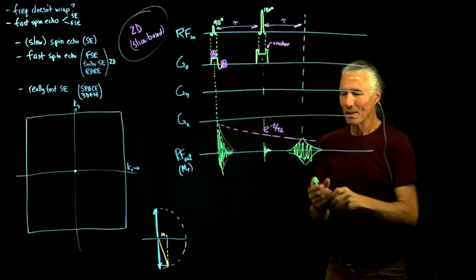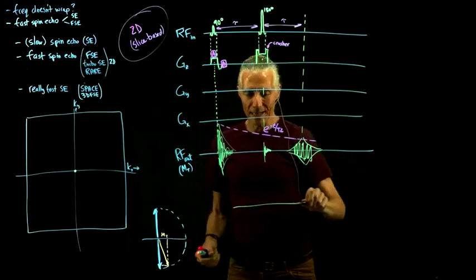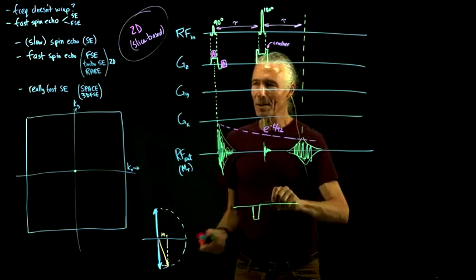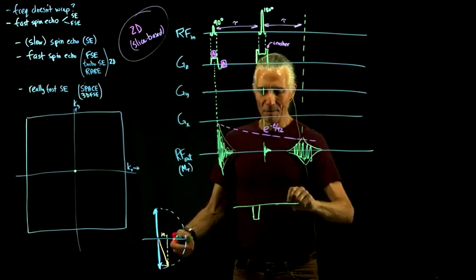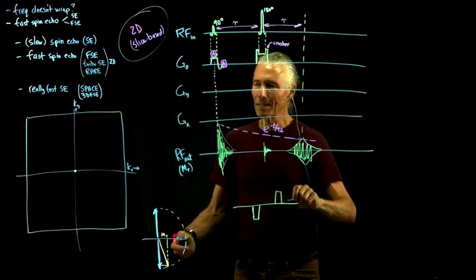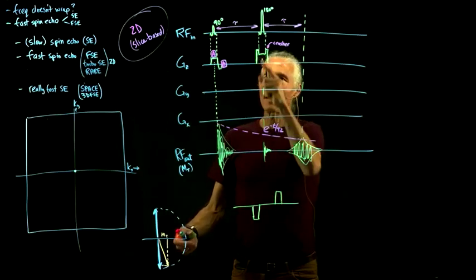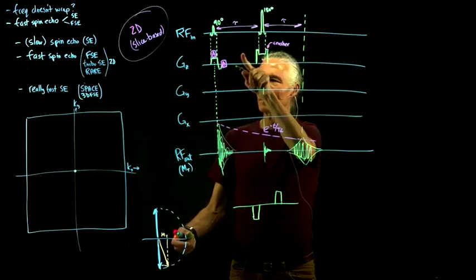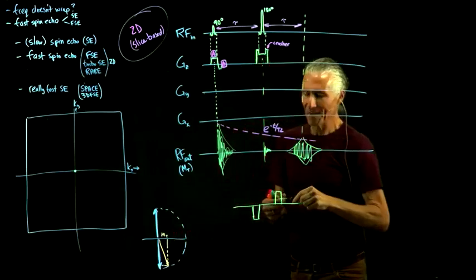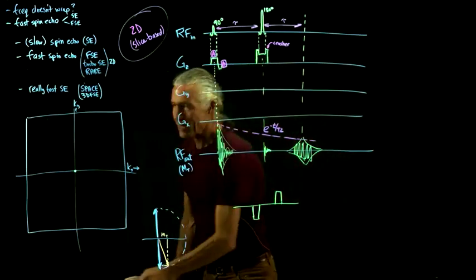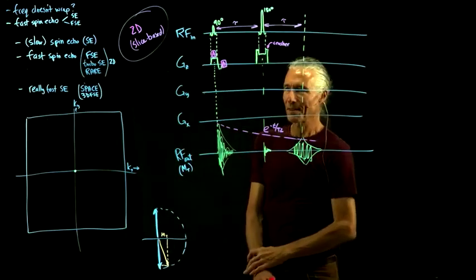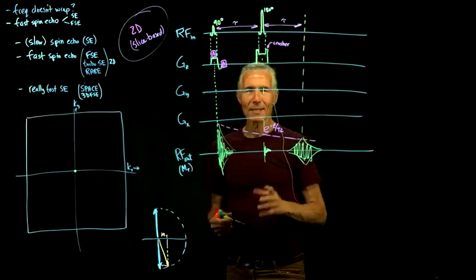Because the 180 is in between, what we're actually doing is essentially pre-messing up the pre-existing transverse magnetization, and then afterwards crushing the part we don't want, that came from the 180, but fixing up the part that we wanted to keep, the transverse magnetization that we wanted to keep before the 180. So you always have that kind of thing going on as a way of cleaning up the signal from the 180 that wasn't a perfectly good 180. Okay, so fine details, but it's always done.